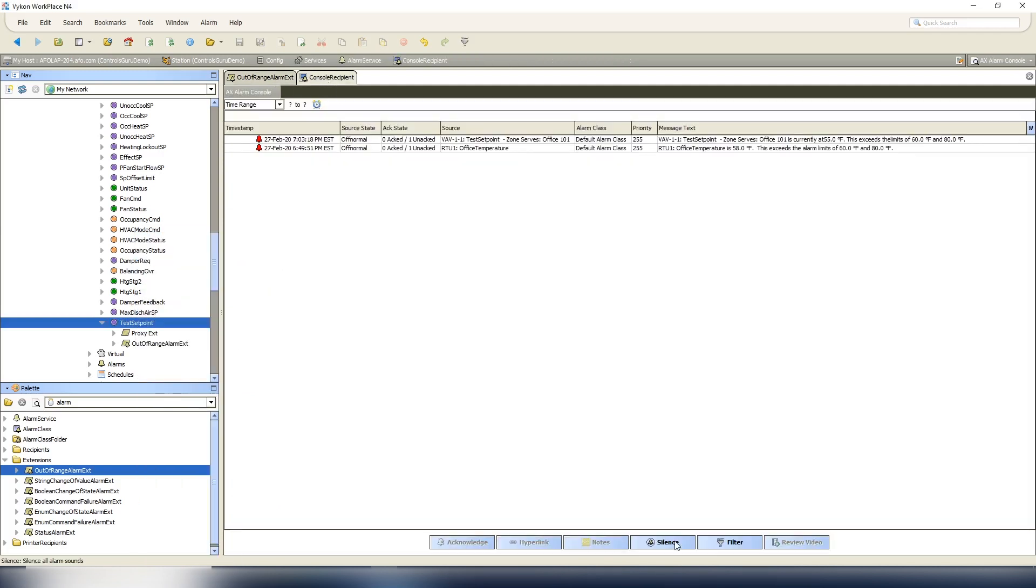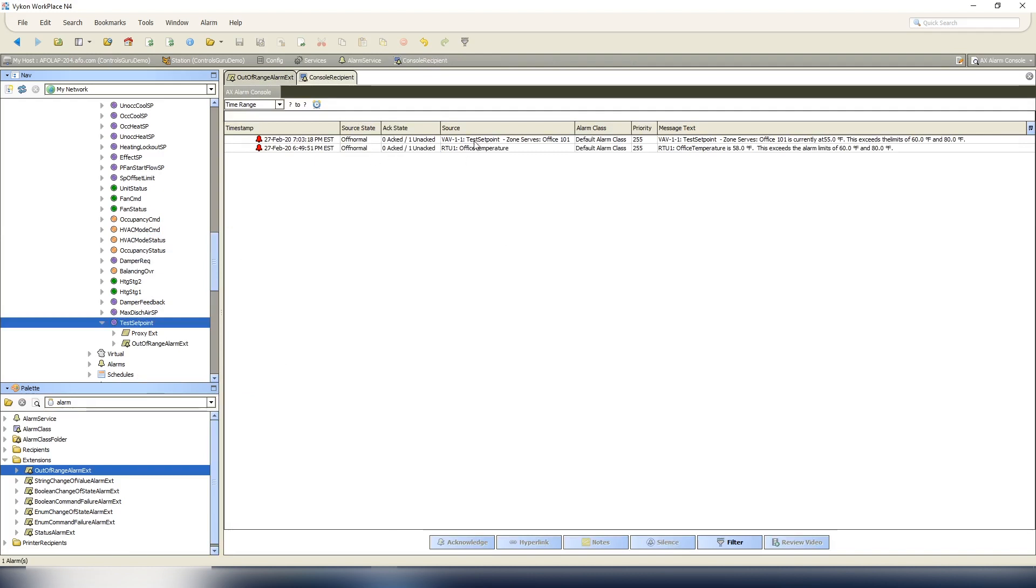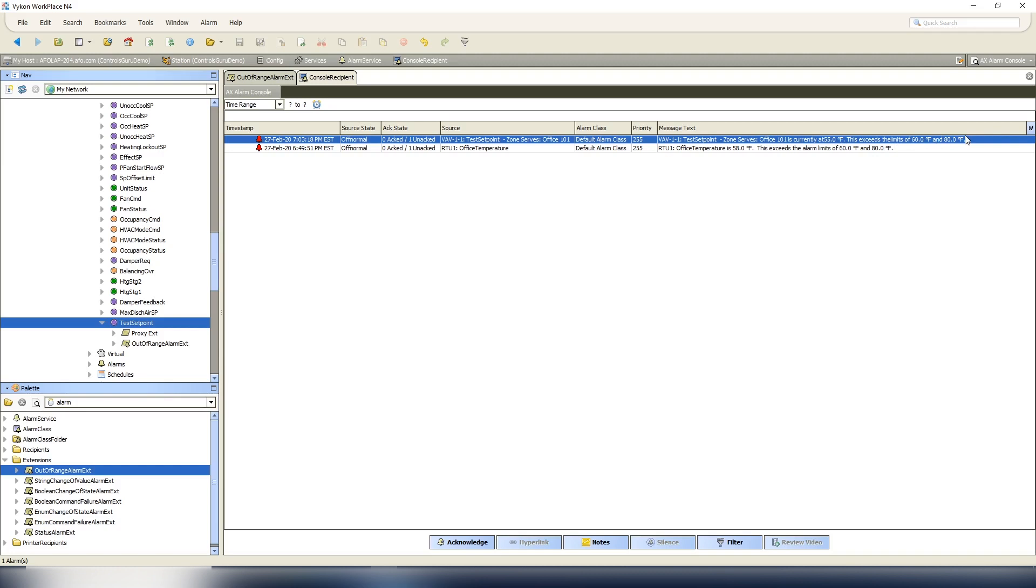It triggered the alarm and here it is. Now it says VAV 1-1 test set point, so it's named what VAV, what the point name is, and then where it serves. And then it repeats that same information. Test set point zone serves office 101 is currently at - I missed the space so we can go back and correct that later - at 55 degrees Fahrenheit. This exceeds the limits of 60 degrees Fahrenheit and 80 degrees Fahrenheit. So again, all the important information in that alarm context all at once.